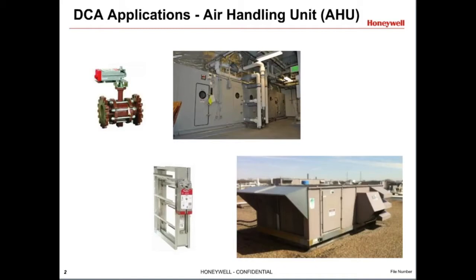This is the position the actuator goes to when power is removed. It may be either normally open or normally closed. Air handlers need to bring fresh air into the building, and the actuators for these outdoor air dampers are usually normally closed. Some air handlers use hot or chilled water through coils to condition the air. These often use valves that are controlled by direct coupled actuators and may be normally open or normally closed.